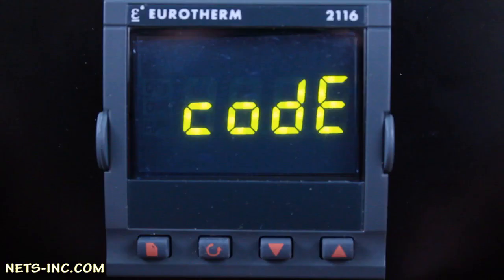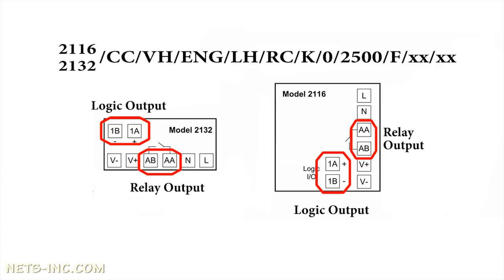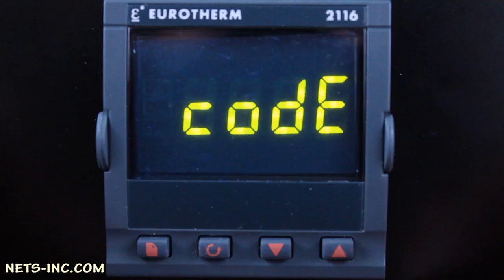This video tutorial will demonstrate the basic configuration level setup of a Eurotherm 2132 or 2116 controller. The 2132 or 2116 is a fixed hardware configuration instrument, which means it comes standard with a logic output on terminals 1A and 1B, and a relay output on terminals AA and AB. For this demonstration, we will consider it set up as a heat or cool controller, with the logic output as the heating output, the relay output as the cooling output, and the process input as a type K thermocouple in degrees Fahrenheit.